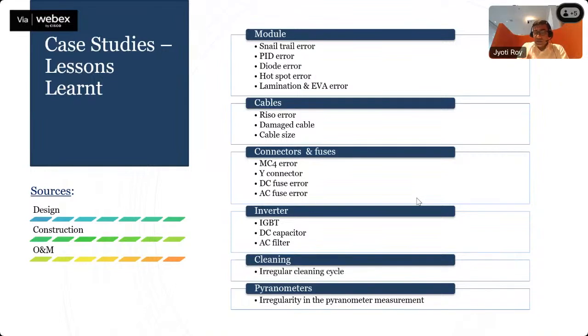But don't go beyond the allowance or limited range given by the OEM, otherwise you will breach the inverter warranty. So how do you really identify the issue? The more pragmatic approach we take is by considering whether the design that went in was appropriate or not. From our experience, the reasons for errors come from design, from poor construction practice, and some lack of O&M activity.